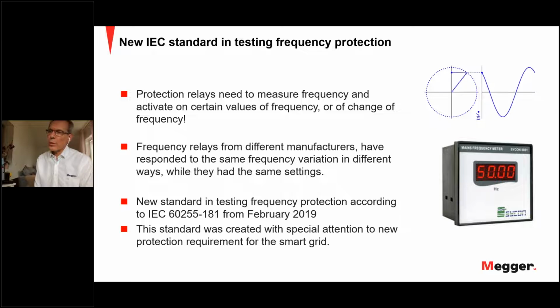And as I said before, and Andrea was speaking about in Monday's session, a new standard was released for testing frequency protection. Protection relays need to measure frequency and activate at certain values of a frequency or of a change of a frequency. Frequency relays from different manufacturers have responded to the same frequency variation in different ways while they have the same settings. So this is really difficult when you are out testing with different manufacturers, because of the variation in the relays' algorithm to measure the frequency.